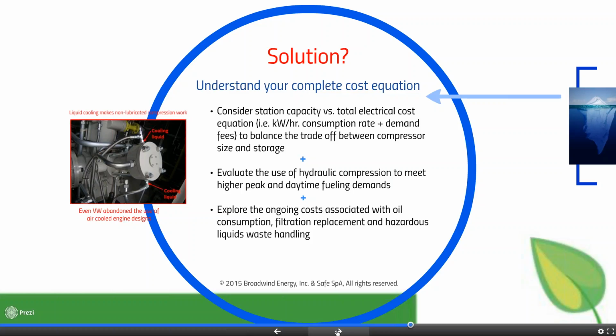So how do you look at these issues and deal with them in your design? When you're looking at the overall station capacity and the size of your compressors, I think it's definitely worth looking at smaller compression that can get the job done. So you're looking at your storage, you're looking at future growth and how you can manage that with a minimum cost, and you're looking at keeping an optimum size in your motors to ensure that you don't run into excessive demand charges any more than you need to. If you can keep your main motors to the smallest size possible that can still deliver the fuel you need in a given demand period, that's going to be key to keeping your operating costs down on a monthly basis.